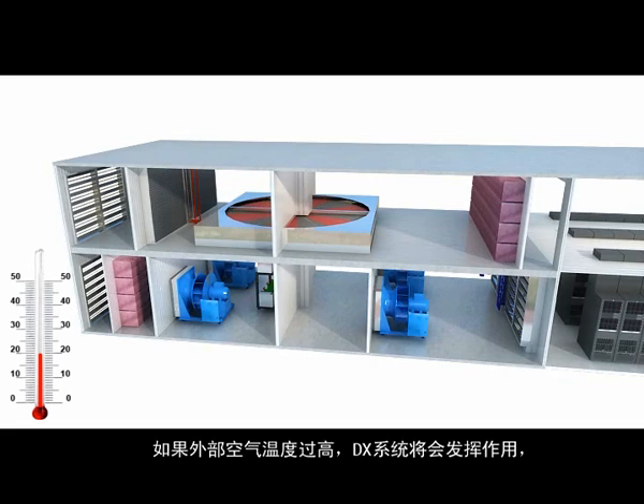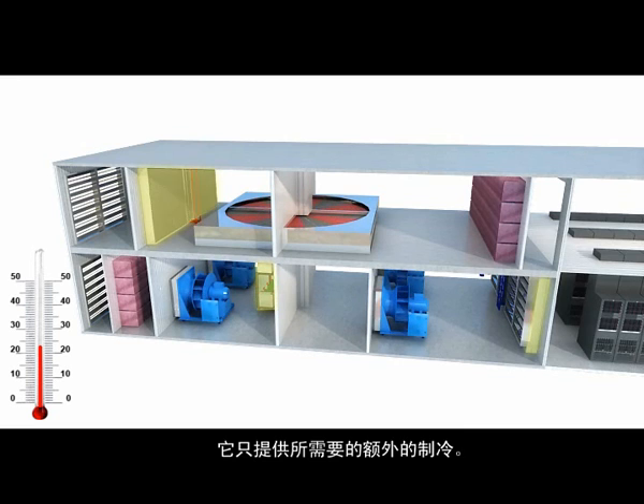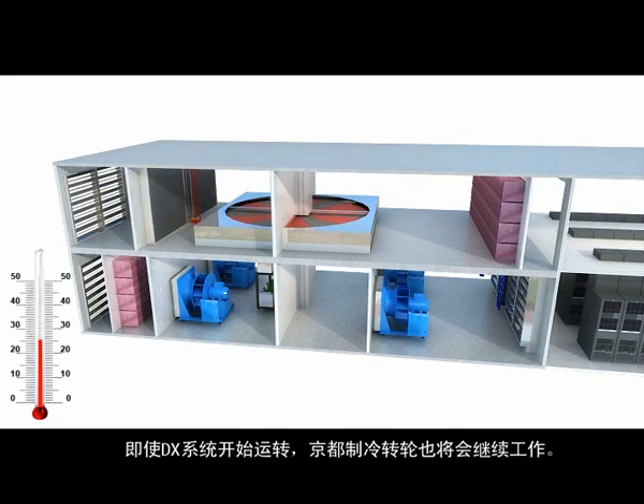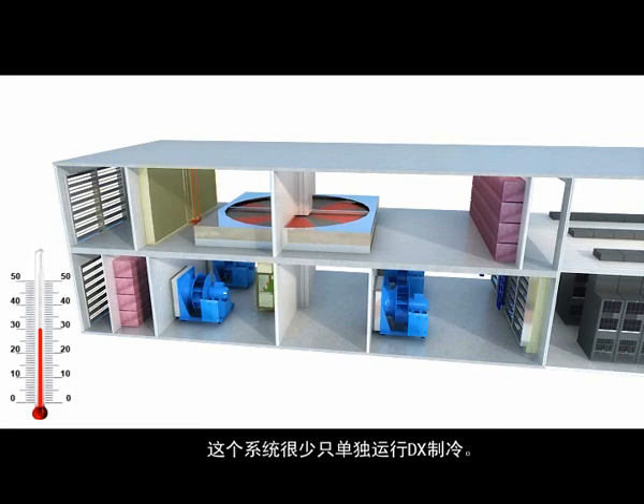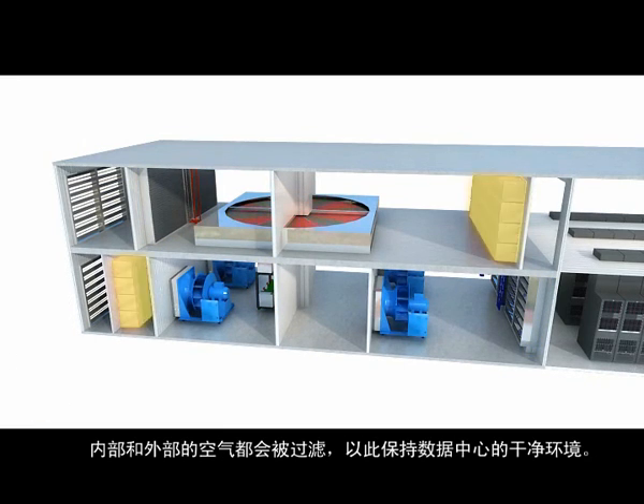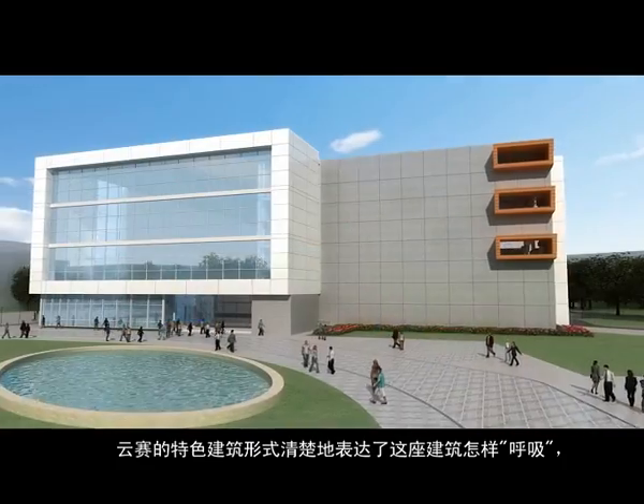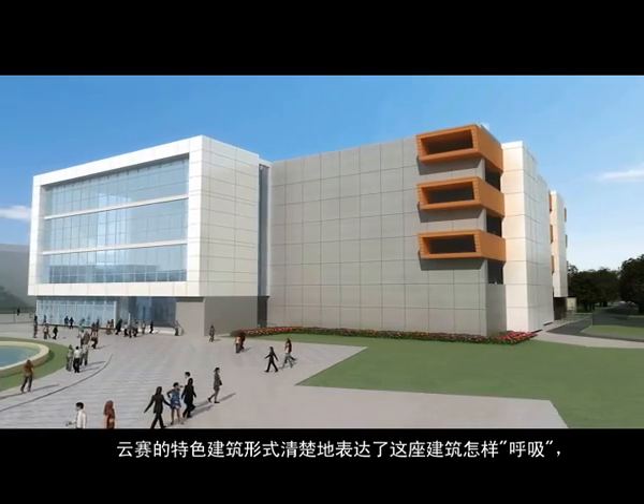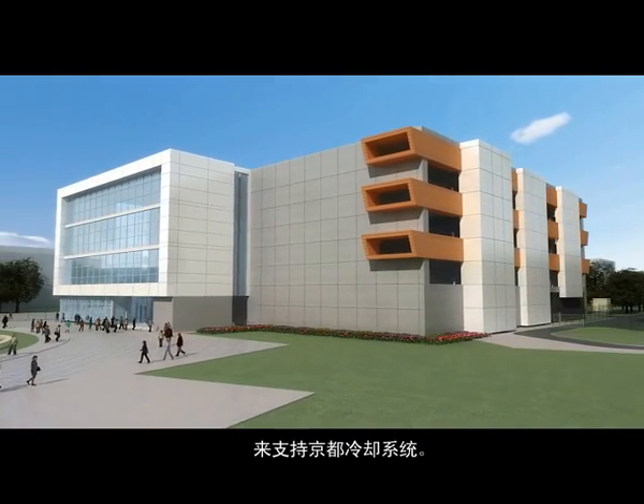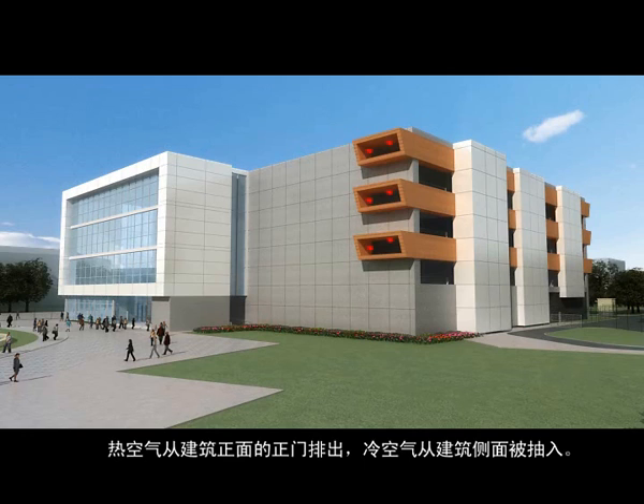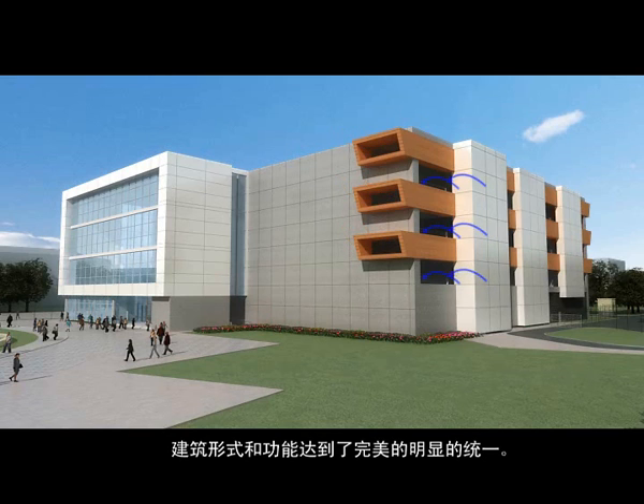If outside air temperatures are very high, the DX system begins to provide only the amount of additional cooling that is required. The KyotoCooling wheel continues to provide benefit even after the DX system begins to assist. The system rarely operates on DX cooling alone. Both inside and outside air is filtered to keep the data center clean. Cloudsite's dramatic building form clearly indicates how the building breathes to support the KyotoCooling system. Hot air is discharged from portals on the front face of the building, and cold air is pulled in through the sides of the building. The building form and function are fully integrated and visible.